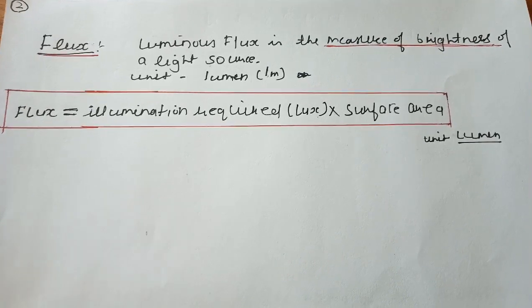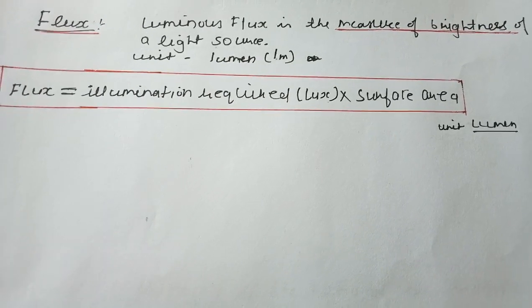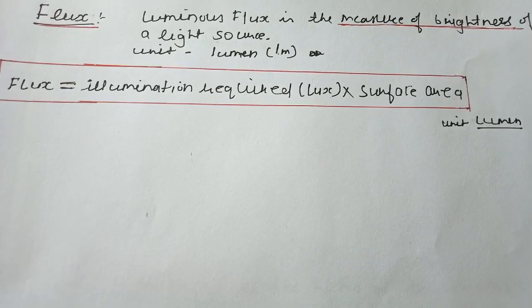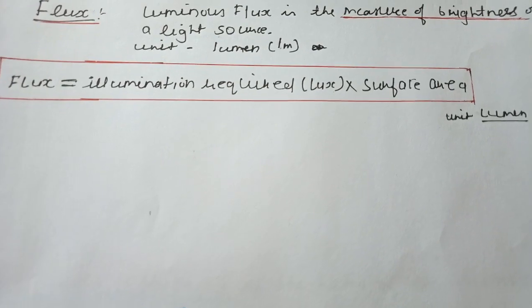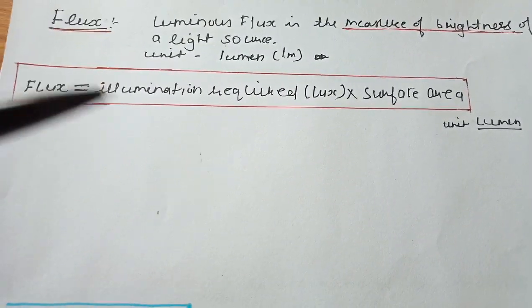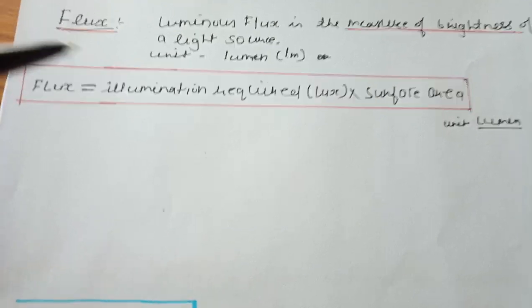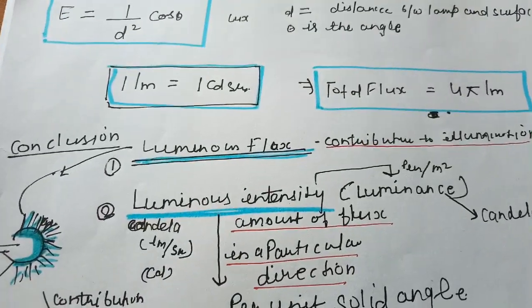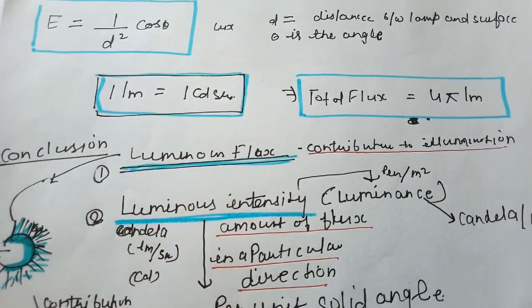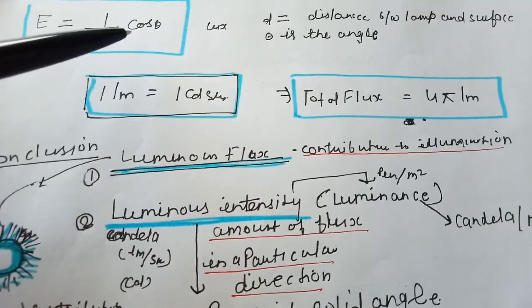Luminous flux is the measure of the brightness of a light source. It is denoted by lumen. By formula, flux equals the illumination required multiplied by the surface area. Luminous flux represents how bright a light source is and how it contributes to the illumination level of a room. Illuminance can also be defined using the inverse square law: E equals I over d squared multiplied by cos theta.